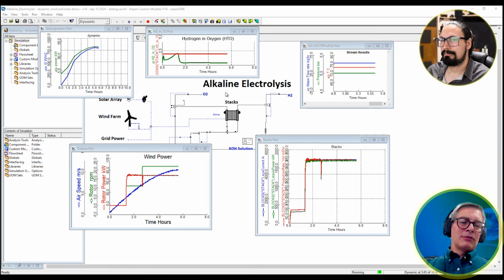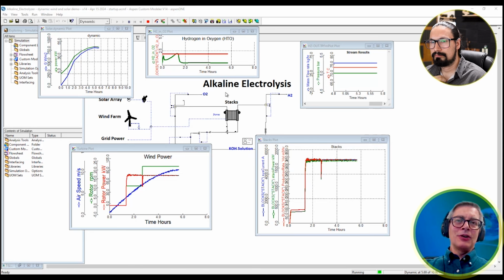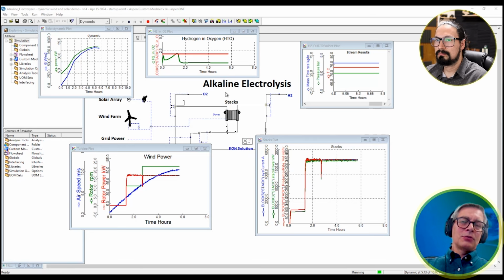You might represent, say, 10,000 life cycles of the plant, considering all the random phenomena that can occur. At the end, Fidelis will tell you the expected overall capacity over a long period of time, given your current topology and the expected performance of the equipment. It will also tell you which bad actors you have—what parts of the system are the biggest source of loss of capacity.